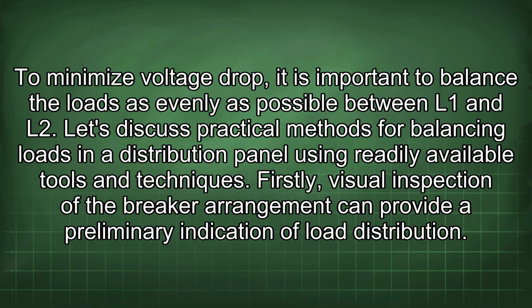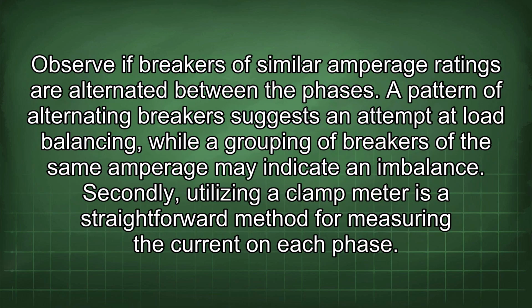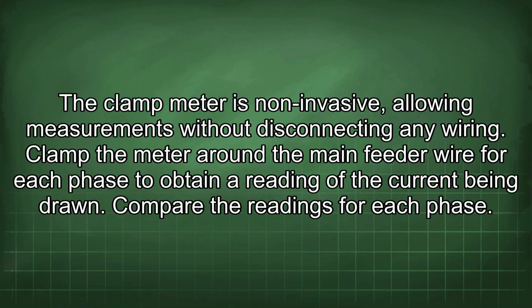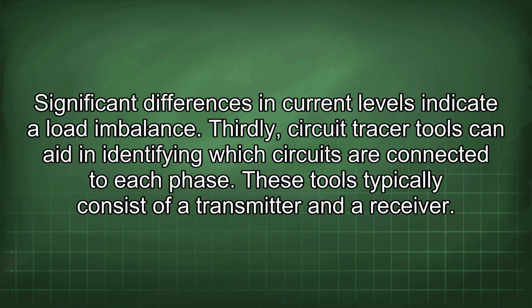Firstly, visual inspection of the breaker arrangement can provide a preliminary indication of load distribution. Observe if breakers of similar amperage ratings are alternated between the phases. A pattern of alternating breakers suggests an attempt at load balancing, while a grouping of breakers of the same amperage may indicate an imbalance. Secondly, utilizing a clamp meter is a straightforward method for measuring the current on each phase. The clamp meter is non-invasive, allowing measurements without disconnecting any wiring. Clamp the meter around the main feeder wire for each phase to obtain a reading of the current being drawn. Compare the readings for each phase. Significant differences in current levels indicate a load imbalance.